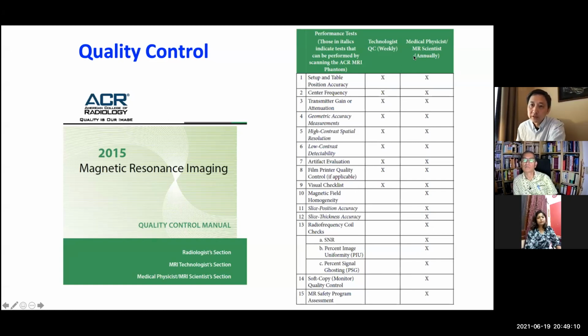And annually, this is what physicists need to perform. In addition to the weekly QC, physicists will also perform magnetic field homogeneity, slice position accuracy, slice thickness accuracy, and RF coil check. The RF coil check includes signal to noise ratio, image uniformity, percent signal ghosting, and also monitor soft copy QC, and also MRI safety program assessment.